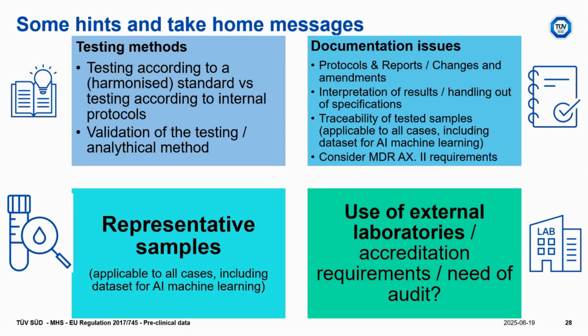which samples have been used for testing, how many, and the justification of the sample size, in correlation with the design requirement. And we expect that in the report, it's very clear what you tested, which was the lot, which was the characteristic, which was the environment, and all the items used for testing. And please consider this is applicable to all cases, including, for example, datasets for AI machine learning testing. While for a biocompatibility test, it's very direct that the tested sample is the physical unit. However, we need to know which lot it was, with which material it was constructed, which is the traceability. The same applies when we have tested software, especially AI, where the dataset is critical for the demonstration of performances.